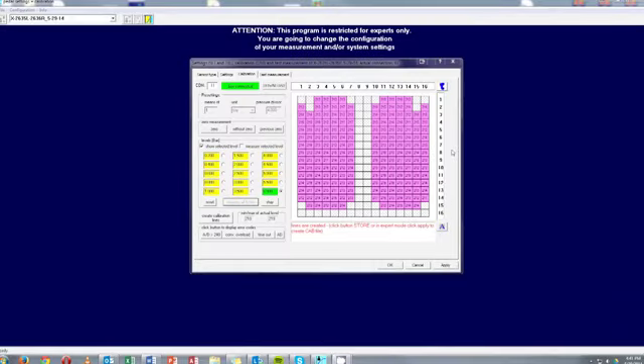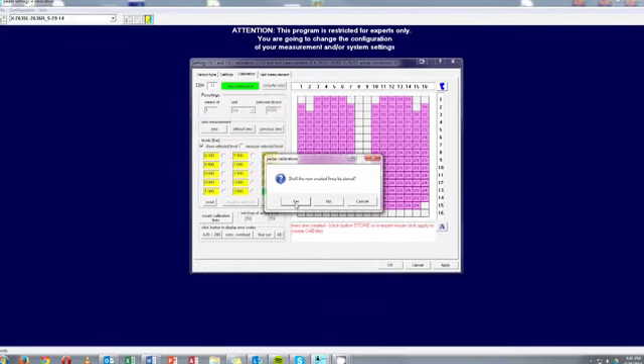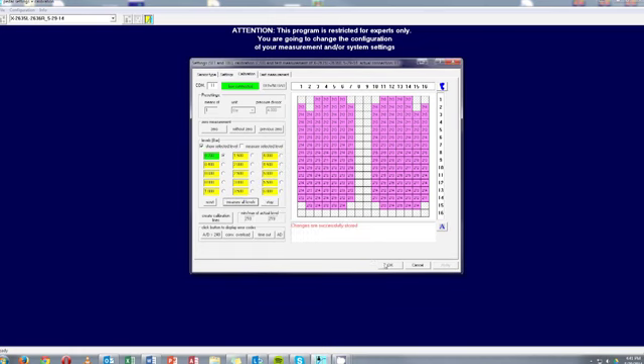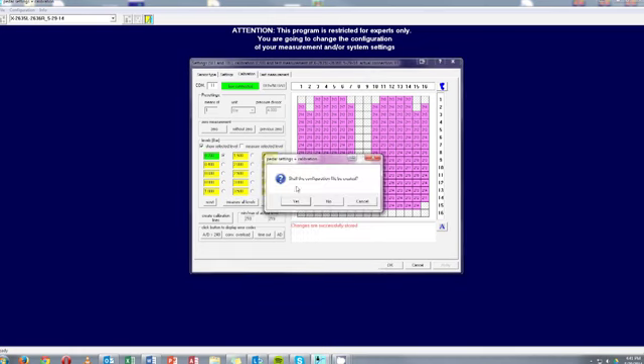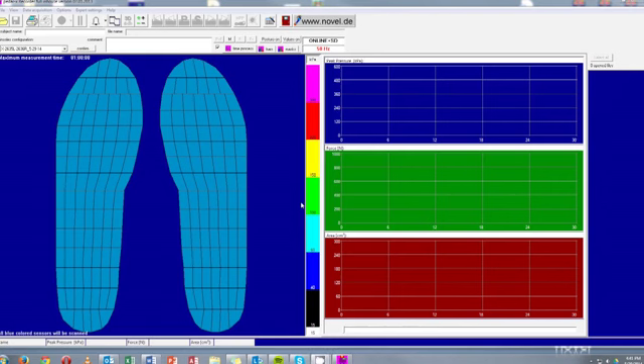Now, in order to finish the calibration process, we click Apply, click Yes to shall the new created lines be stored, click OK, and then Yes to shall the configuration file be created. Notice that the new calibration appears as an option in the drop-down menu.